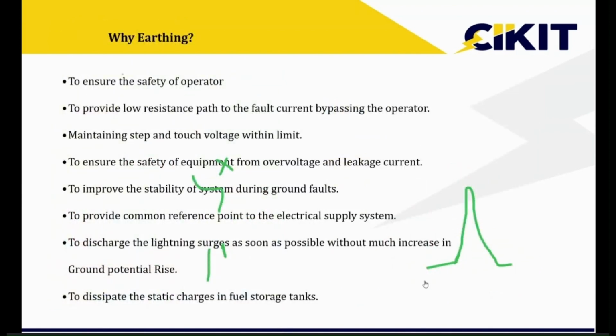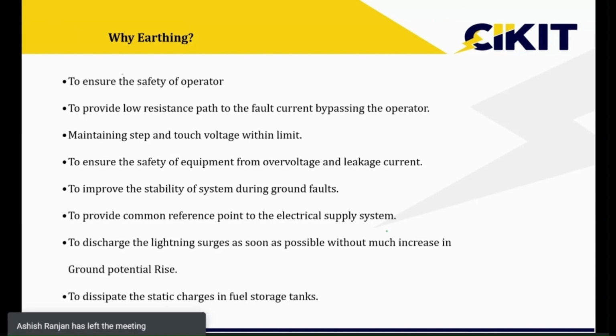Fine. So what is the purpose of earthing? As I mentioned, the primary purpose of earthing is to ensure the safety of people. Apart from that, if we have 230 volt or 240 volt, then we should have a reference point. The earthing acts as a reference point. If you are going for substations, the earthing should be designed to keep the step and touch voltages within the limit. And one more thing: in substations, you will have a lot of protective equipment, and for the proper operation of these protective equipments, earthing is very much essential.